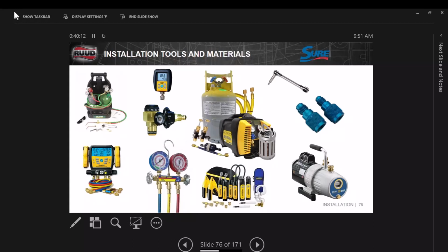How can we find an A2L approved? It'll say it. All of the Appion, the JB, Fieldpiece, they're all putting out nothing but A2L stuff right now. All of the Fieldpiece gauges that you have, the A2L refrigerants are already built into that, so that normally you would go for 134a or 22 or 410A, now you can go to the 454B. Right, and if you bought a set in the past 5 or 6 years, it already has 454B on it.